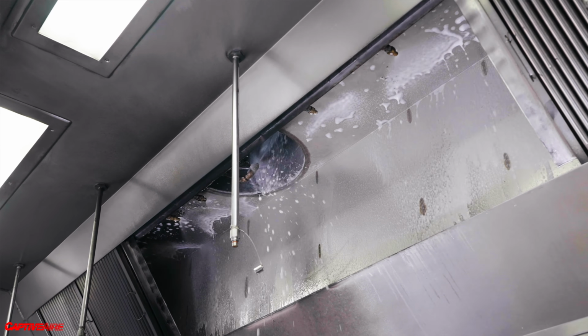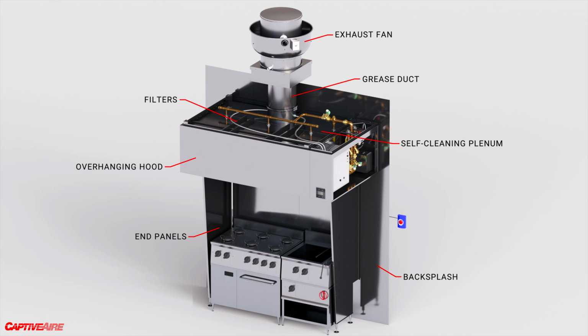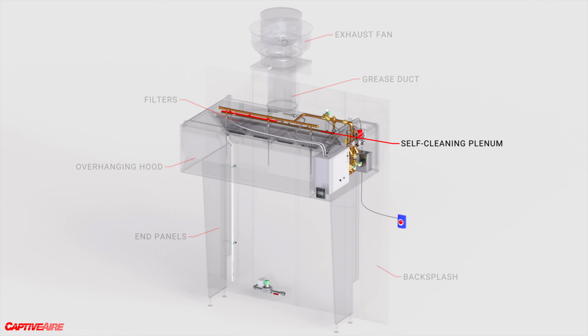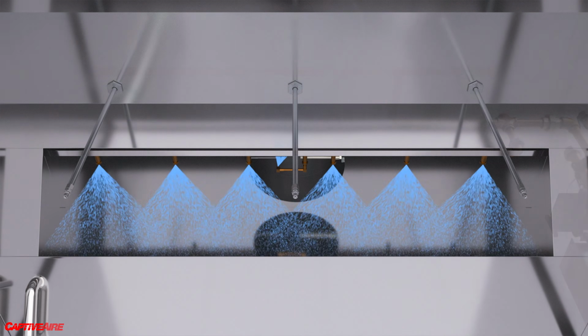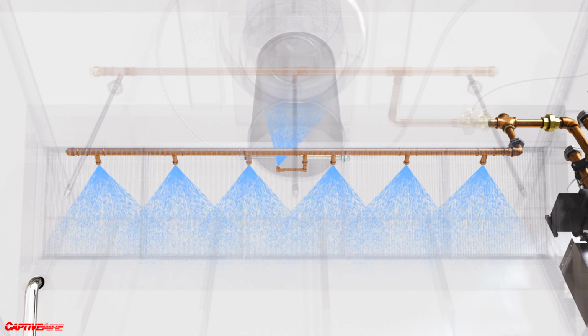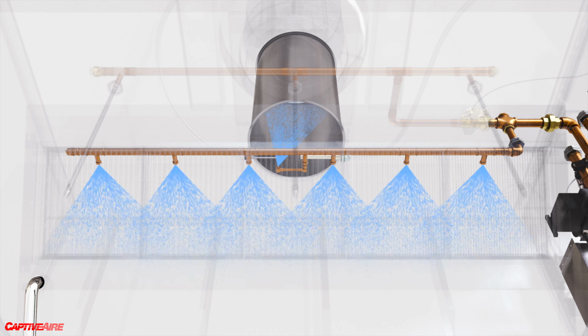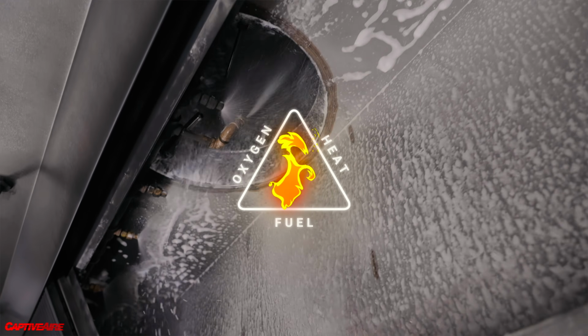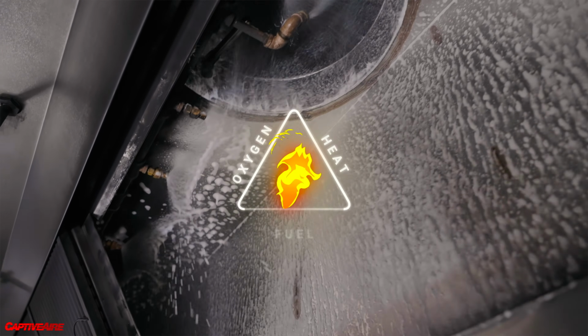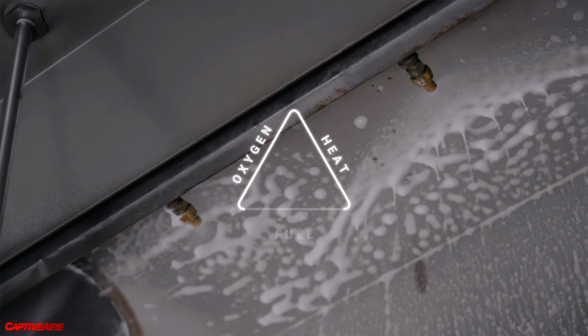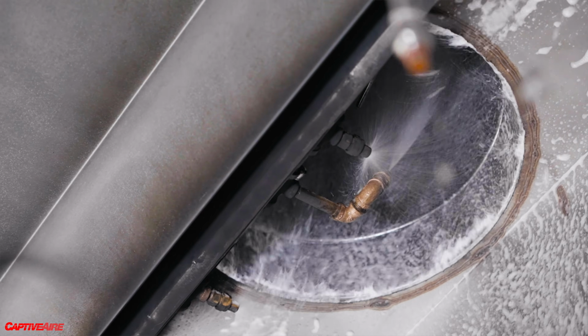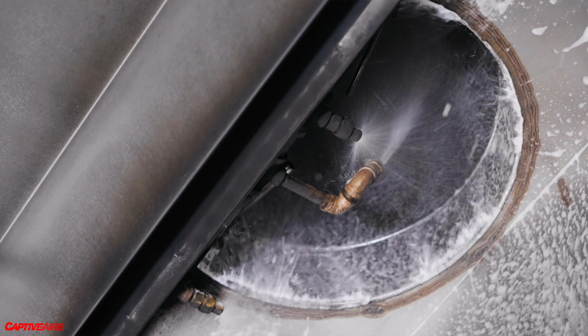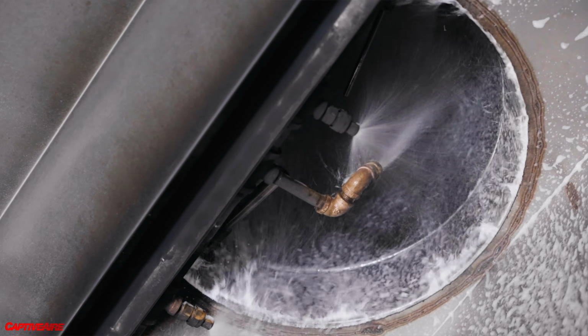There's one aspect of core that is somewhat underrated, and that's the cleaning ability of core, the self-cleaning ability. So we self-clean the hood plenum and duct every single day after cooking appliances start to cool down. So why do we do that? It seems like maybe that's excessive to some people. Well, it's very important for this reason. If you don't have a fuel source, you can't have a fire. So by eliminating that fuel source in the duct and plenum every single day, we reduce the risk of fire.